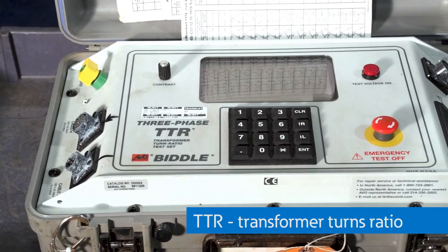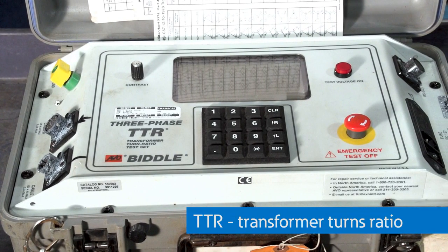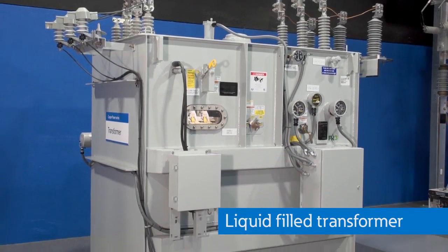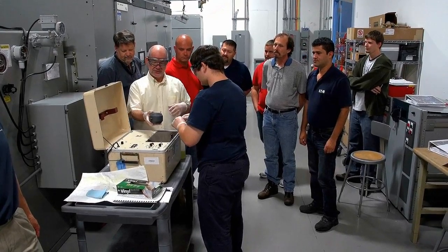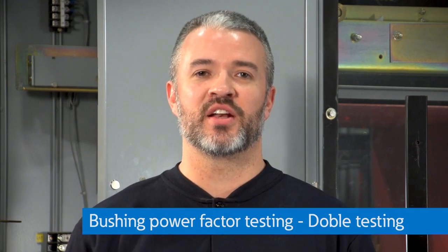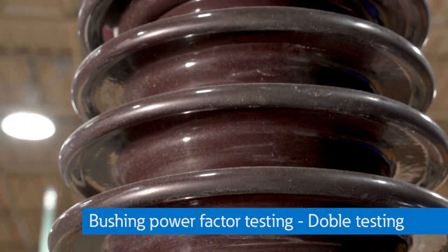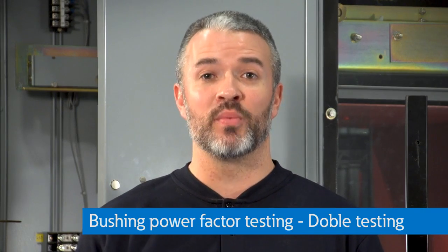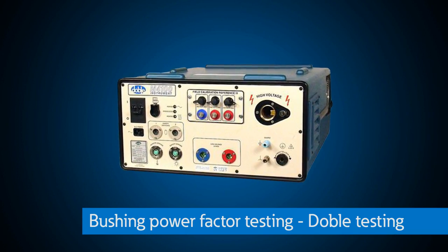There are several other functional and electrical tests that may be performed on electrical equipment to ensure safe and reliable operation. Transformers require special testing to ensure that they operate properly and will continue to operate for their expected life. Transformer testing typically includes TTR, or transformer turns ratio, and Megger testing for dry type transformers, and also includes oil testing for liquid filled transformers. The oil testing evaluates contaminants and helps to determine the health of the transformer. For larger transformers, bushing power factor testing is done to verify the integrity of the insulation of the bushing.